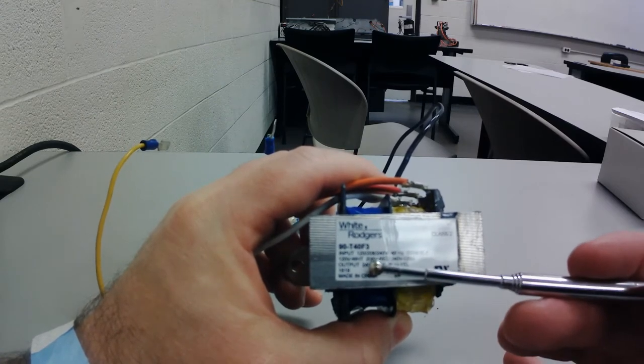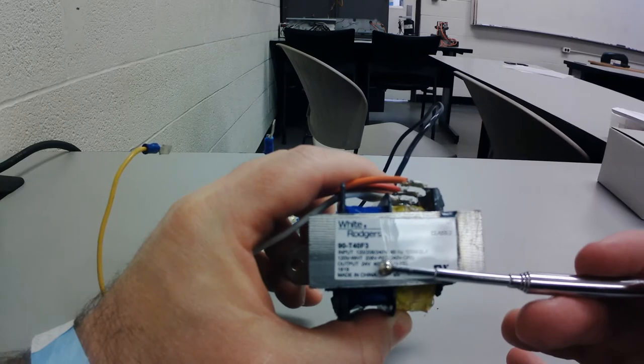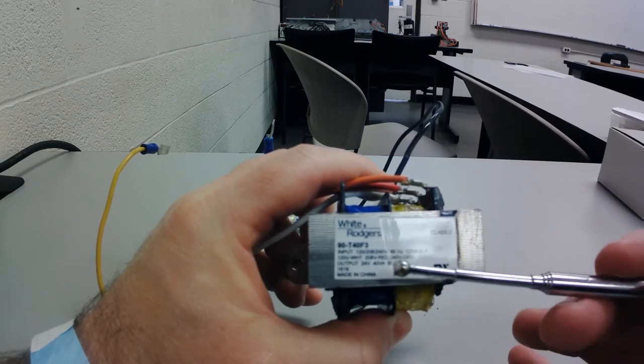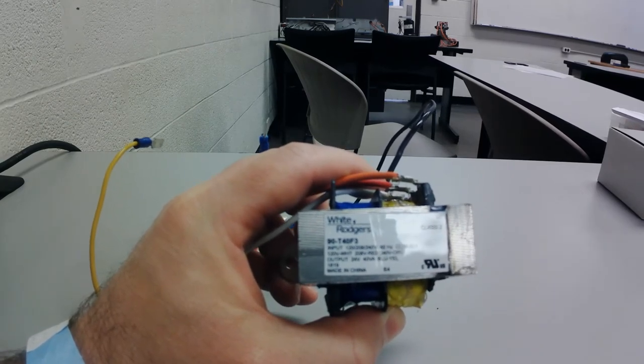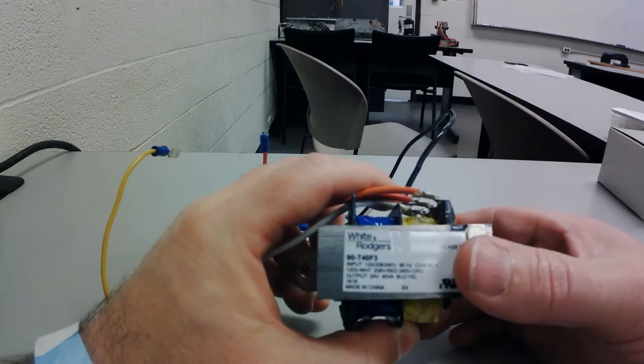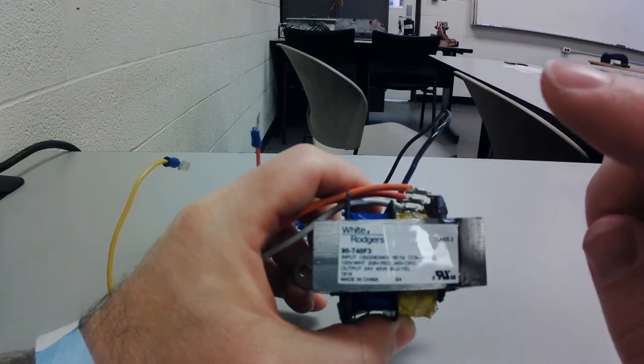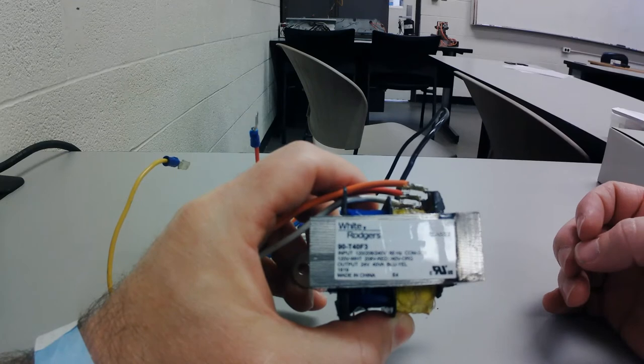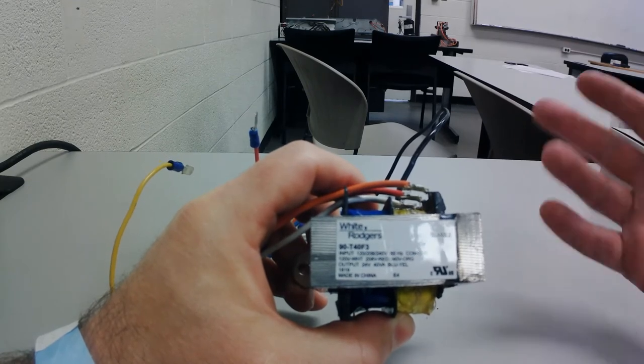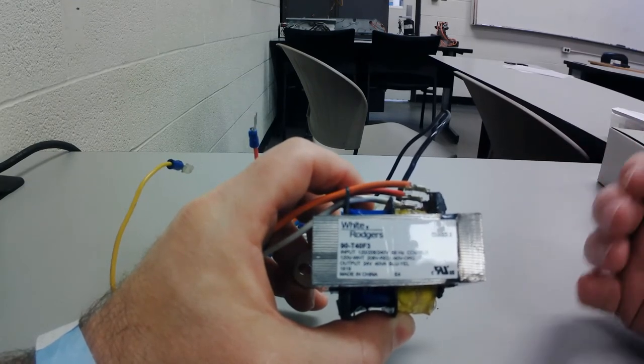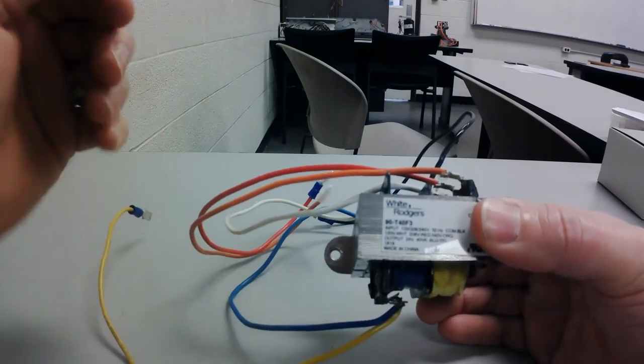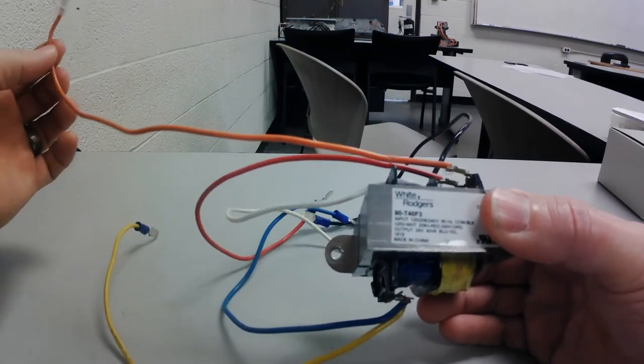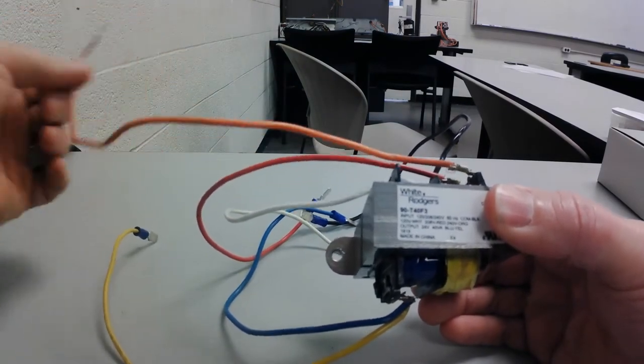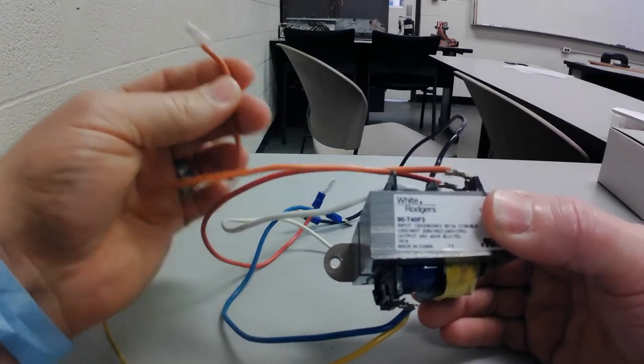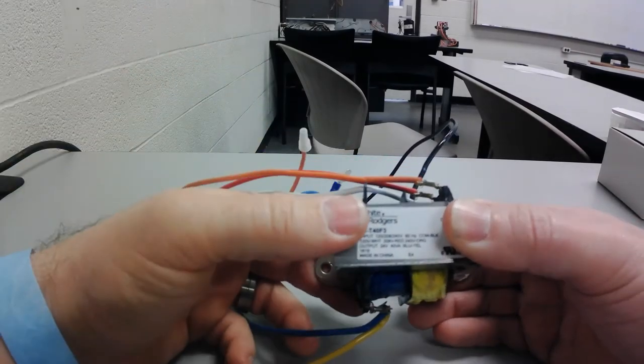And likewise for the 208 and the 240, you would use the appropriate colored wire, and then you would have two unused wires for the primary side of that transformer. And you can't leave them dangling. You don't want to cut them off. You want to leave them there. You may wind up one day repurposing this transformer if you use any scrap parts for personal use. But you don't tie those together.